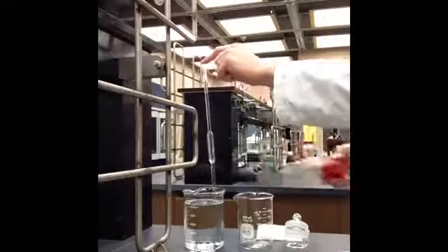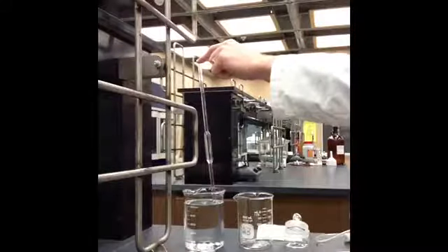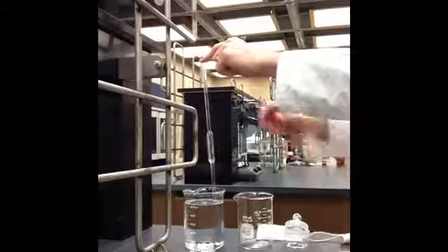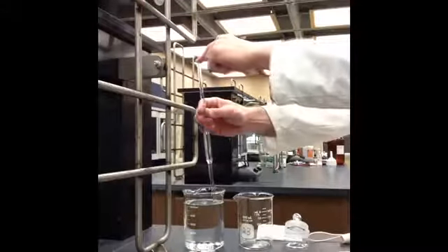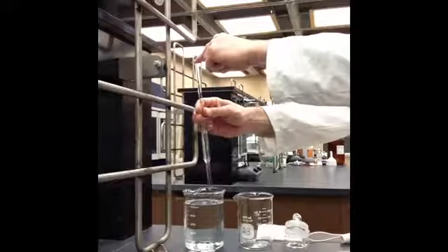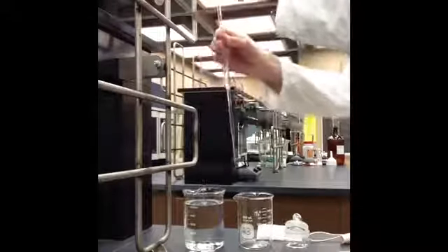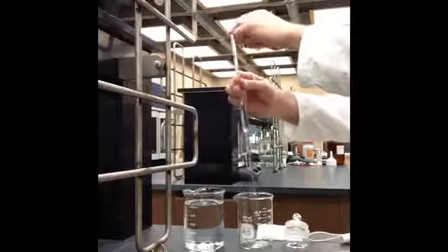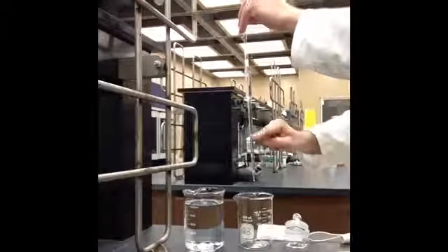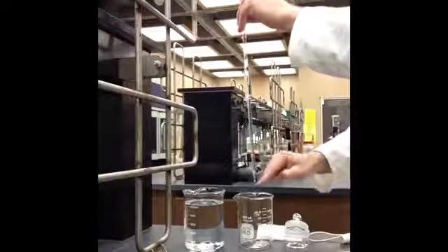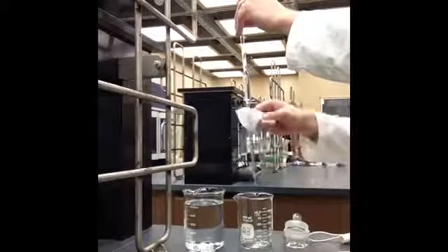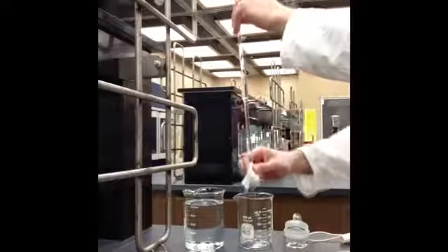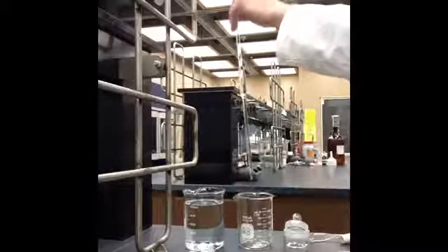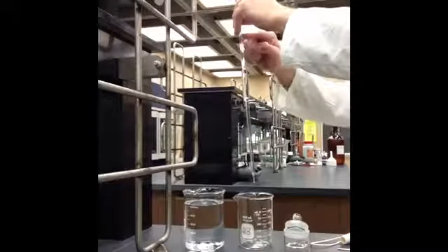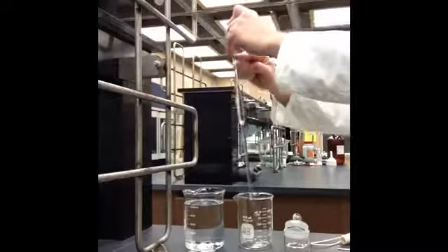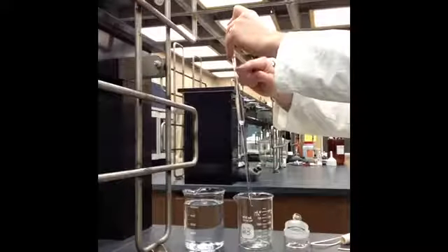You can take the pipette bulb, you're done with that, and now you can lift the pipette out of the distilled water into the waste beaker. And you'll note that there's some water on the outside as well as there may be a drip. So now what we do is we wipe the pipette with the Kim wipe before we bring the line down to the calibration line.